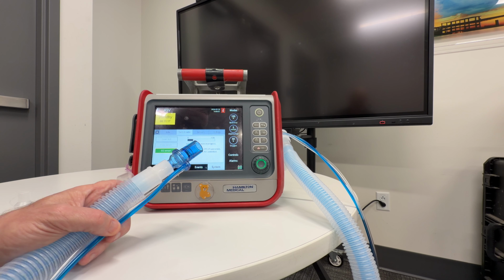All right, now we are going to get a pediatric, and we know that the kid weighs 2 kilos and we're going to have to change circuits. So we unpackage our new circuit. It's going to come with a new exhaust valve, which is pink. So we're going to come over here and we're going to disconnect this one. So a counterclockwise turn and pull it out, set to the side, and you're going to put in this pink one. Automatically it knows that the last test was done on a pediatric circuit. So we're going to know that it's going to alarm.